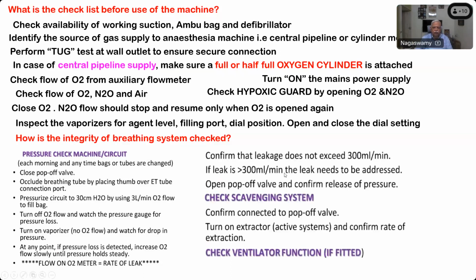So confirm leakage does not exceed 300 ml per minute. If the leak is more than 300, the leak needs to be rectified, corrected. Open the pop-off valve and confirm the release of all the pressure. That is how the pressure check for the breathing circuit has to be done. And next is checking the scavenging system. Confirm it is connected to the pop-off valve, turn on the extractor, and confirm the rate of extraction if it is attached to scavenging.